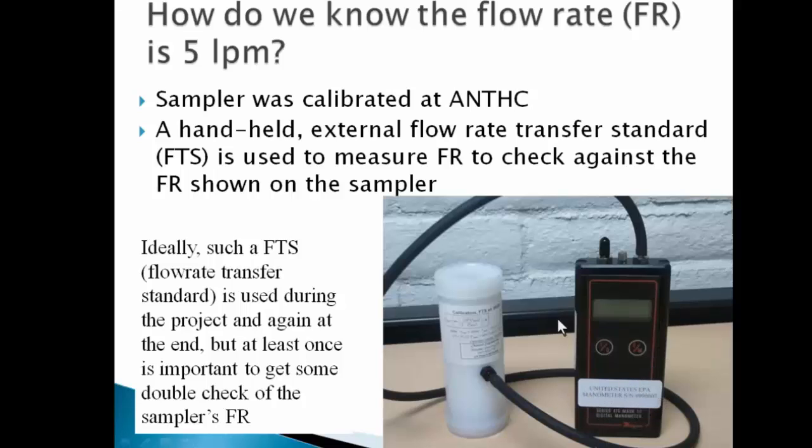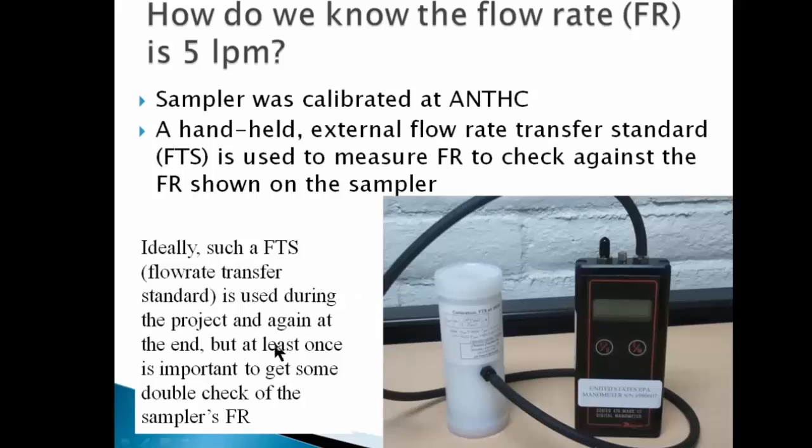We have some of these at the Tribal Air Monitoring Support Center that we loan out to tribes when theirs are sent back to the manufacturer for recalibration. Ideally, such a flow rate transfer standard is used during the project and again at the end, but at least once.